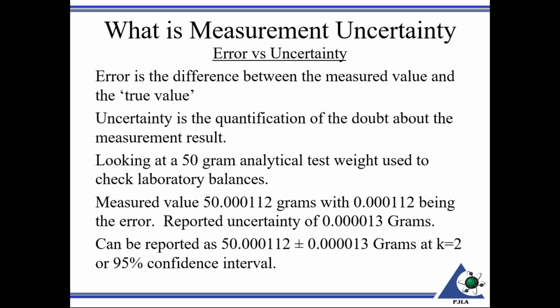However, the uncertainty associated with it, if it's from an accredited calibration lab, should be on the calibration report: 0.000013 grams at k equals 2, or a 95% confidence interval.